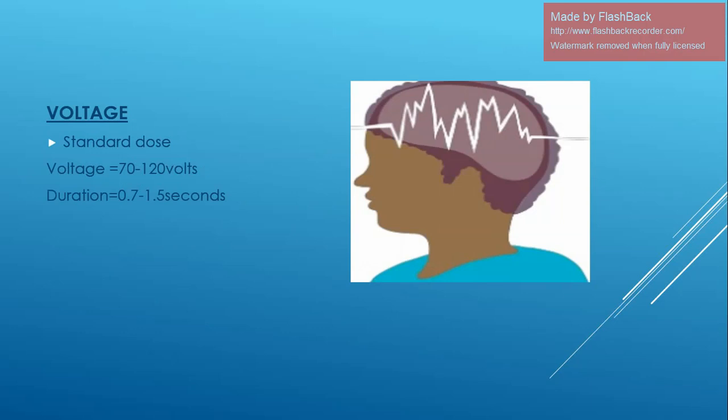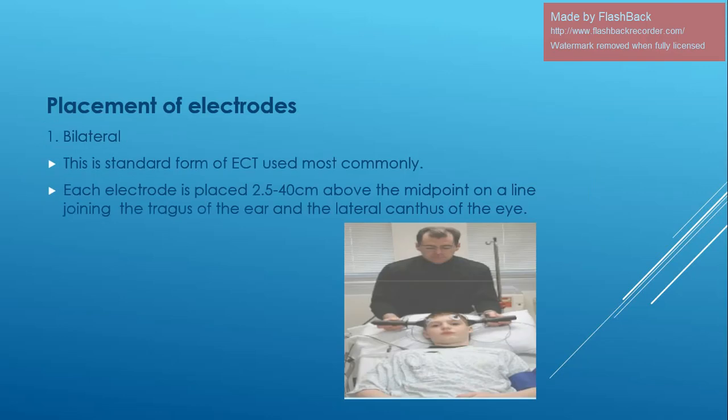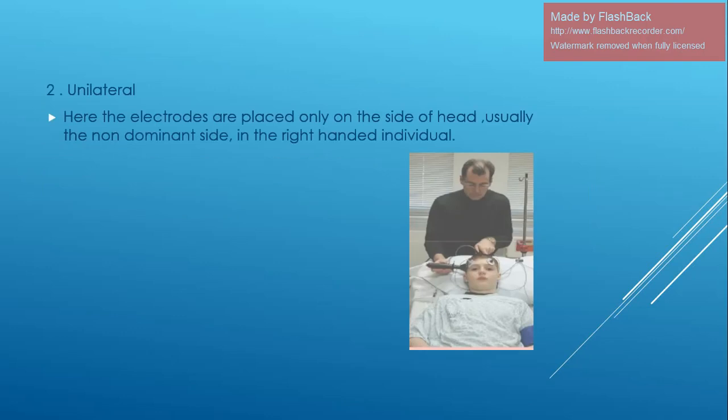The standard voltage used is 70 to 120 volts and duration is 0.7 to 1.5 seconds. Regarding electrode placement — bilateral is the standard form of ECT used most commonly; each electrode is placed 2.5 cm to 4 cm above the midpoint on a line joining the tragus of the ear and the lateral canthus of the eye. For unilateral ECT, electrodes are placed only on one side of the head, usually the non-dominant side in right-handed individuals.